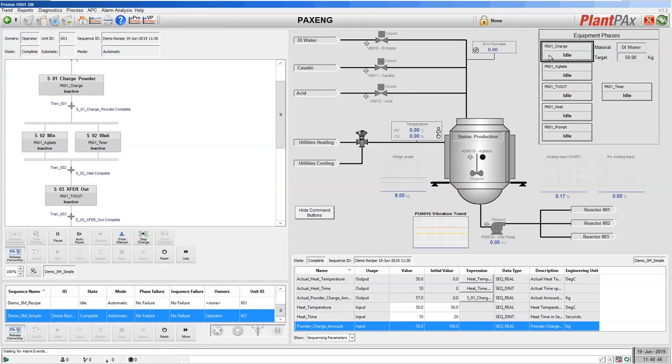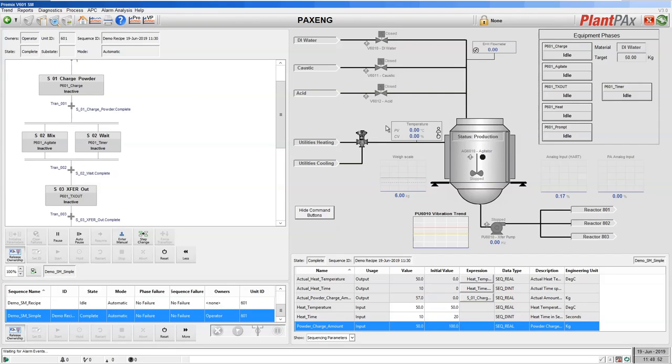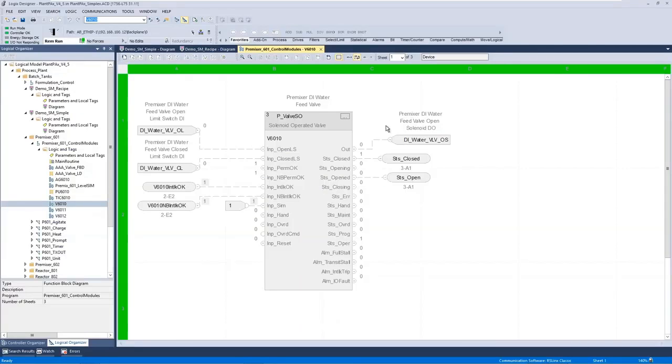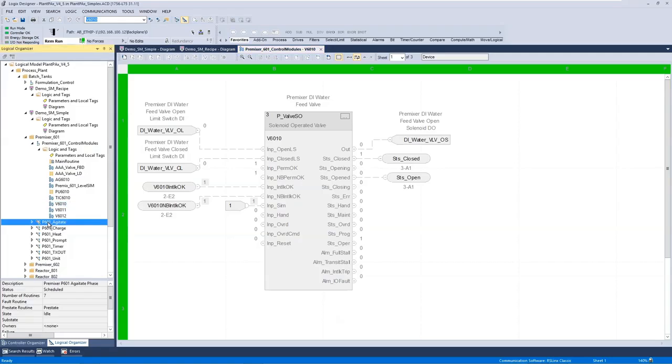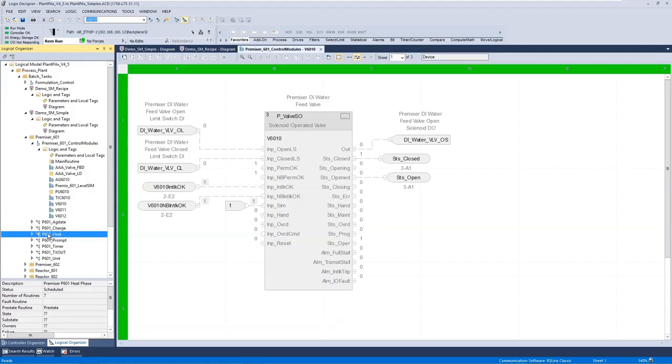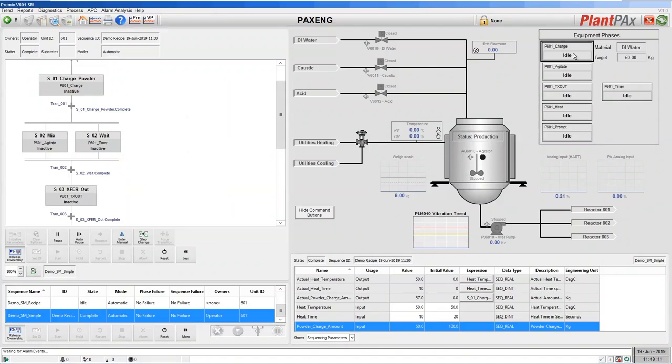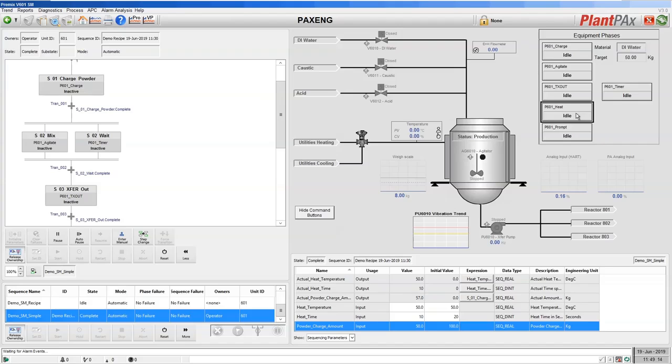To use Sequence Manager, you have to implement these equipment phases using another built-in technology that's available in both Control and Compact Logix called Phase Manager. So here in our controller code, you can see that we have these phases: the agitate, charge, heat, prompt, timer, transfer out, which correspond to these phases shown on the graphic, the charge, agitate, transfer out, heat and prompt.